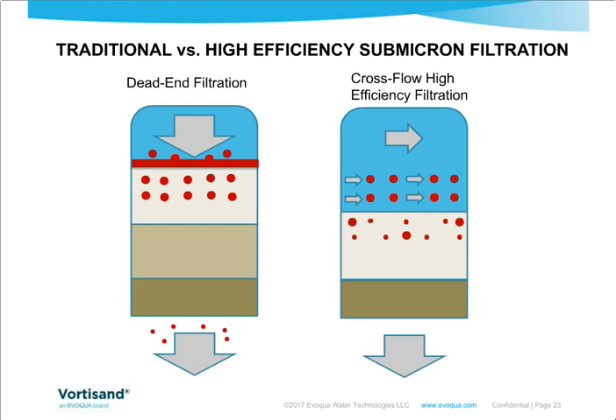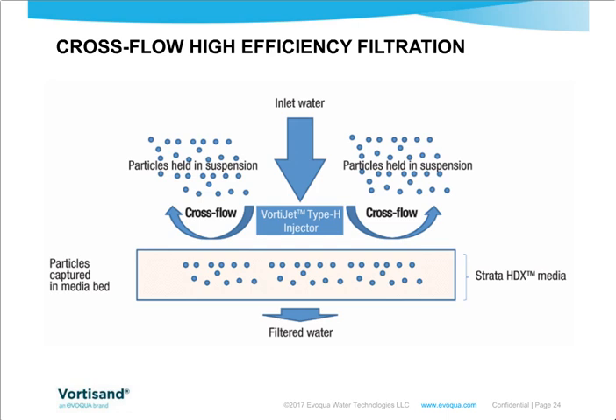If you look at this comparatively to cross-flow high efficiency filtration, you can see some very interesting differences. Here you have the combination of tangential or cross-flow with micro sand media, and the combination of those two allows fine filtration to occur at high velocities. The micro sand that we use is 0.15 millimeters in diameter, combined with VortiSand's VortiJet injector technology. This takes a vertical flow into the top of the bed and translates that vertical flow into a horizontal sweeping effect, allowing larger particles to be scoured and brought into suspension, holding those larger particles in suspension, allowing a fresh open media bed to absorb and trap smaller and smaller particles.